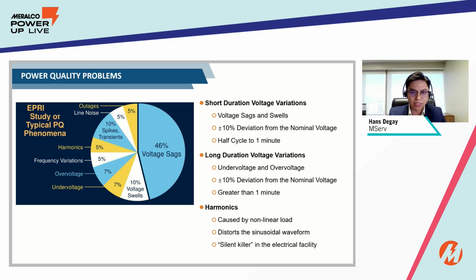So what are voltage variations in the first place? This was also mentioned earlier by Engineer Al, but basically they are fast voltage variations from half cycle to a few seconds, up to a minute. Anything beyond that is already considered long voltage variation. So sometimes sinasabi under voltage, over voltage na matayan kami ng equipment, but actually it could be a fluctuation lang. Other factors are also harmonics and frequency variations, line noises, and outages, amounting to around 5%.